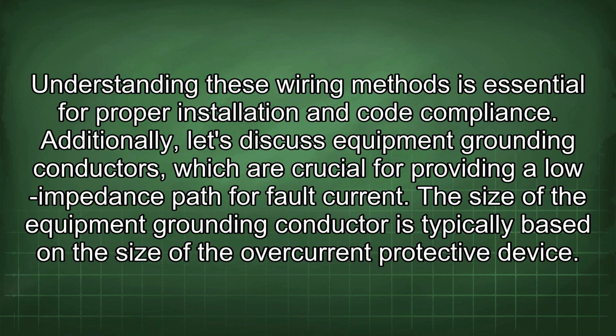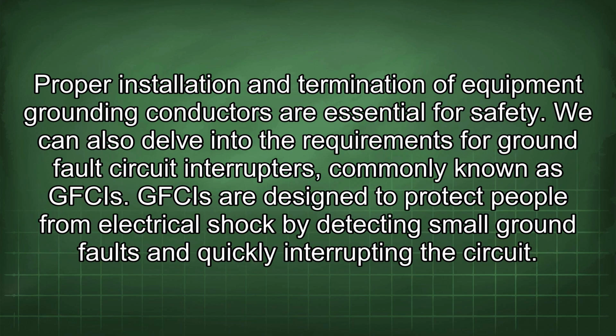Let's discuss equipment grounding conductors, which are crucial for providing a low impedance path for fault current. The size of the equipment grounding conductor is typically based on the size of the overcurrent protective device. Proper installation and termination of equipment grounding conductors are essential for safety.